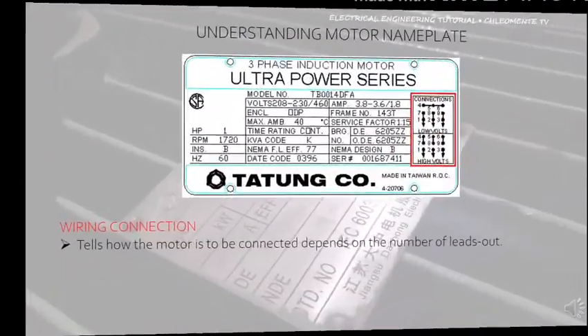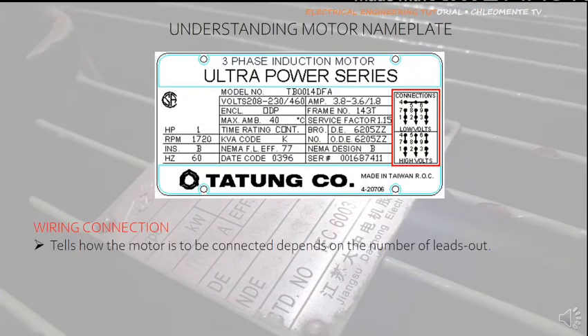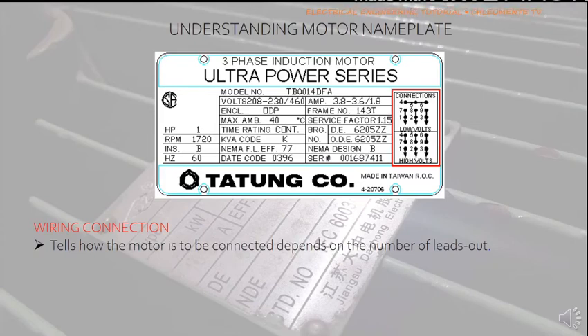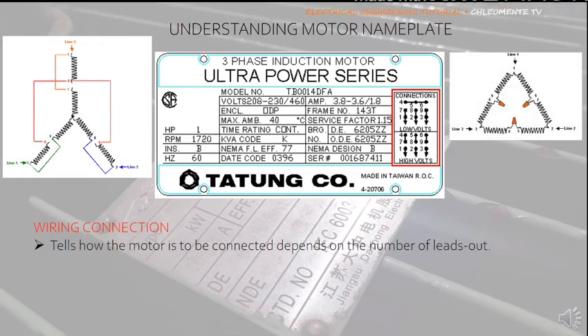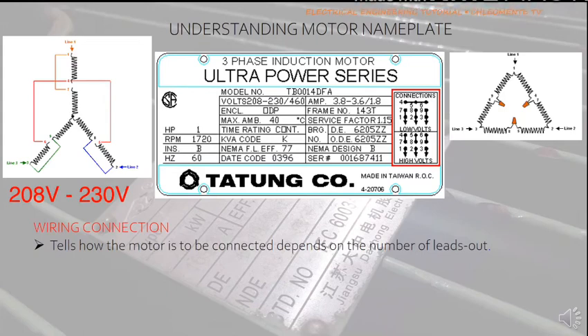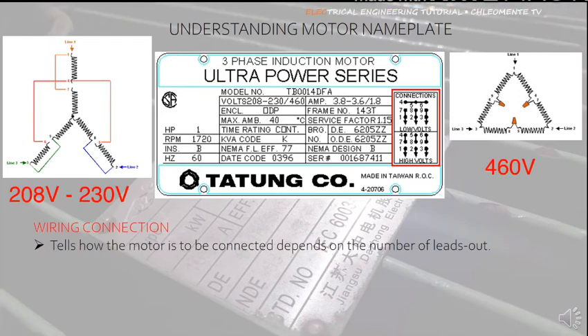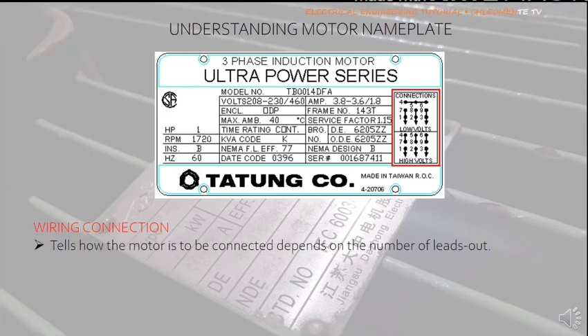Wiring Connection: This data tells you how the motor is to be connected depending on the number of motor leads. Typically, the motor is connected in star or Y configuration for low voltage and delta for high voltage. In this example, when the motor is supplied by 230 volts, it should be connected in Y or star. When supplied by 460 volts, it should be configured to delta. Not doing so may cause the motor to draw high operating current and may cause motor failure.